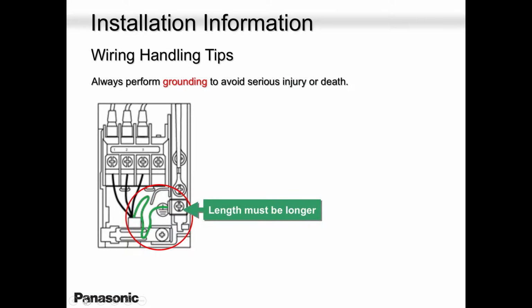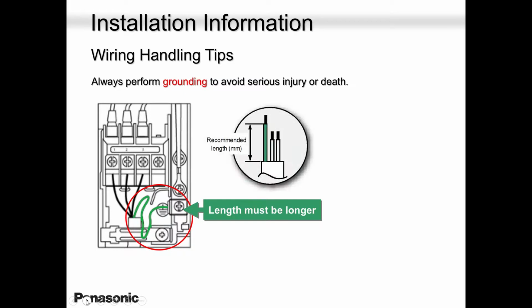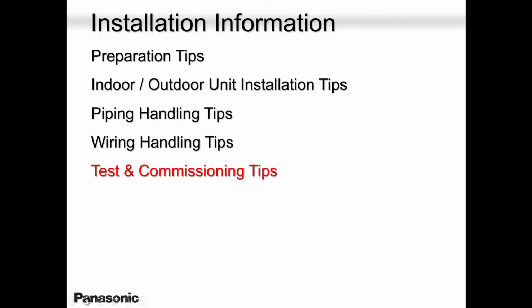Okay, so your power goes to the outdoor unit, and from the outdoor, 3 wires and ground, 1, 2, 3 comes to the indoor unit, and that wire, please also do not join it. 14 gauge is what we use. I went to a job site a while back, and the guy used 18 gauge, and he was getting all kinds of errors. The unit would run fine for 1 or 2 days and then trip.